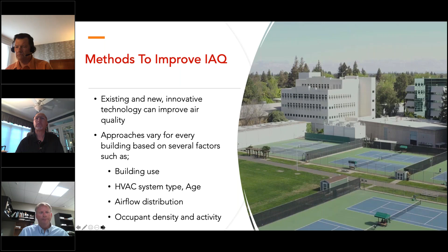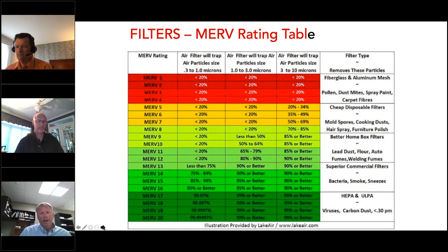So let's talk a little more about filters. Here's a MERV rating table. In most systems, sometimes you have MERV 8 coming standard from the factory. I did a senior housing study a month ago, and they literally had MERV 5 filters in their equipment coming from the factory. Most of that equipment wouldn't even handle a MERV 8 filter. But ASHRAE recommends a MERV 14, with a minimum of MERV 13. When you look at the second column, which is in that COVID particle range, that's when you start trapping some of those particles. We'll talk a little about air cleaning technology that makes particles larger, which will increase the amount of particles we can collect in a filter. We can go all the way up to HEPA filters in some systems, and we'll talk about that too. But then you're getting into the MERV 17 and higher filters. Next slide.